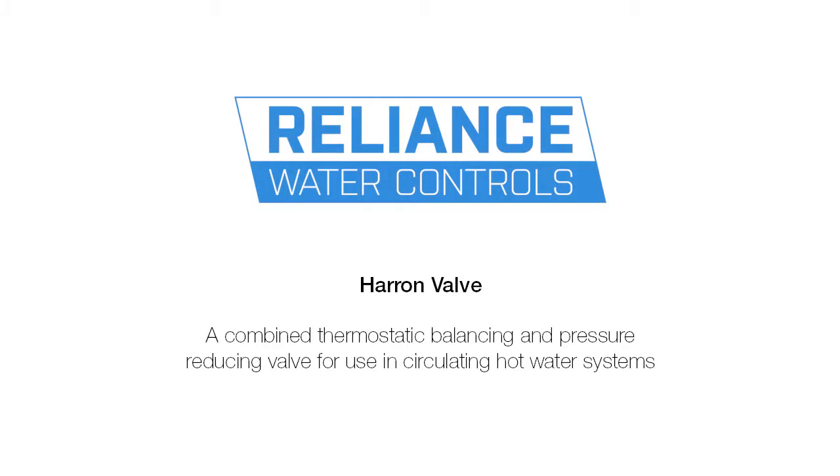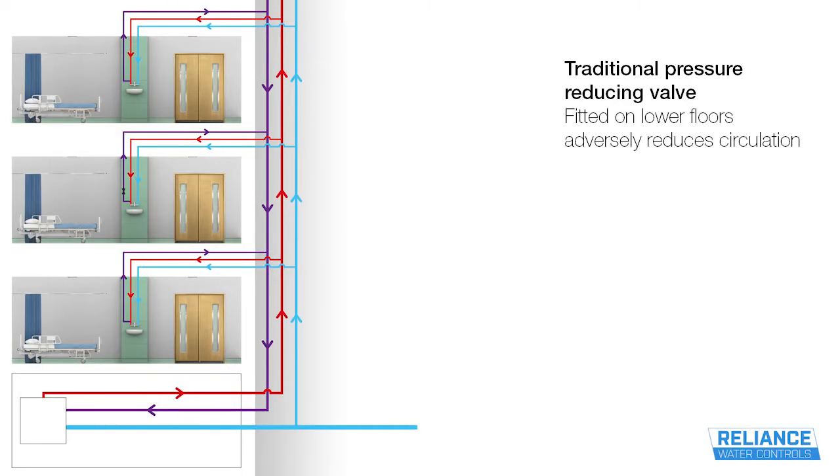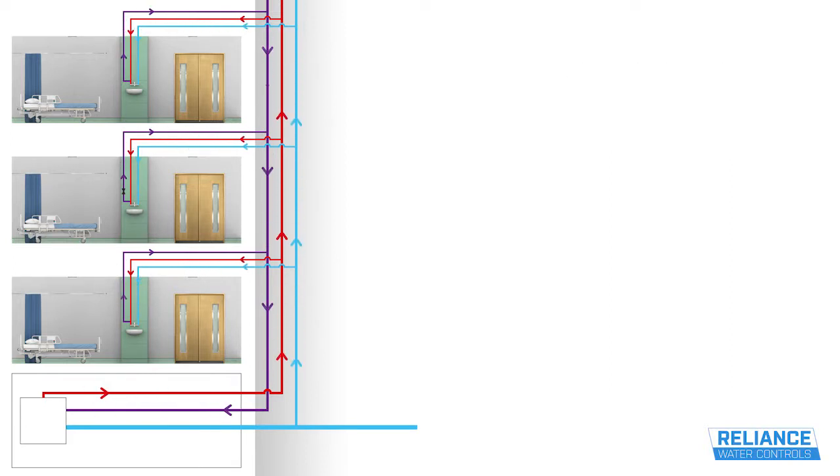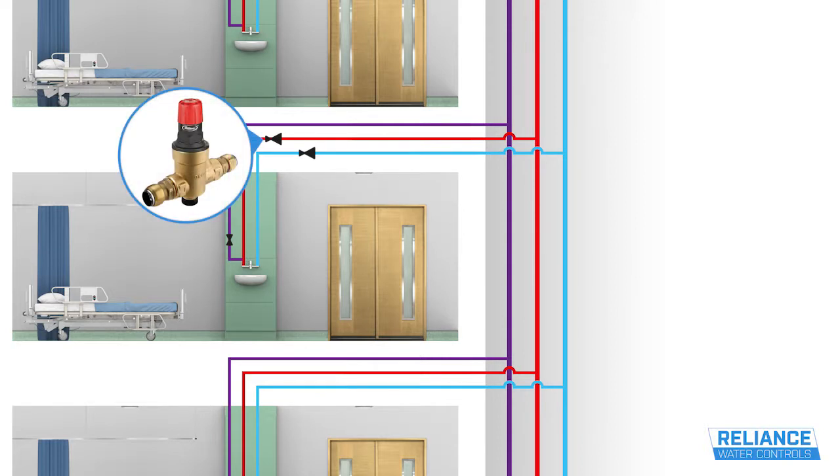Introducing the Harron Valve from Reliance Water Controls. When fitting pressure-reducing valves to a hot water circulating system, it is important to make sure they are installed in the correct location. Water will not circulate through a pressure-reducing valve, so they must be installed after the point where the primary and secondary pipes connect together, or circulation will stop.